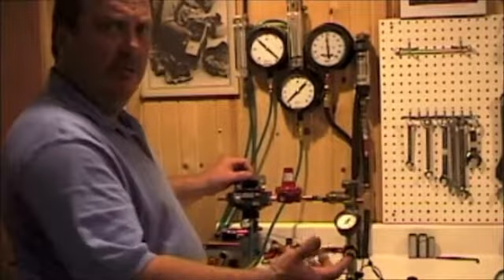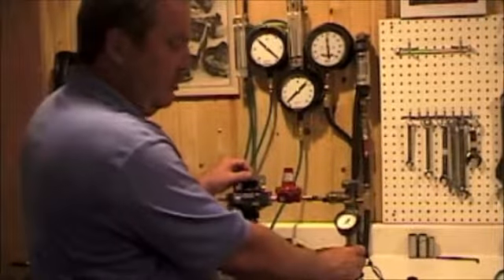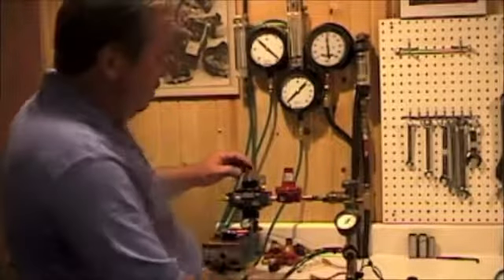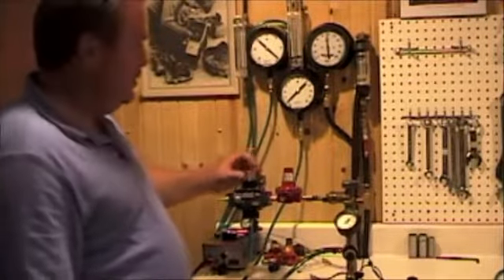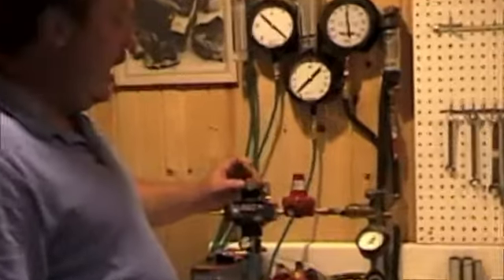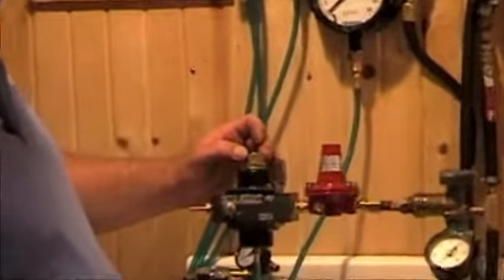In some applications, we want to have higher start times. We'll call it a 5 pound start time. So I simply go to this knob. It says start time right on the top of it, high and low. You'll need a 7/8 and a 1-inch wrench to make this adjustment. At this point, it's still loose, so it can be adjusted with your fingers.